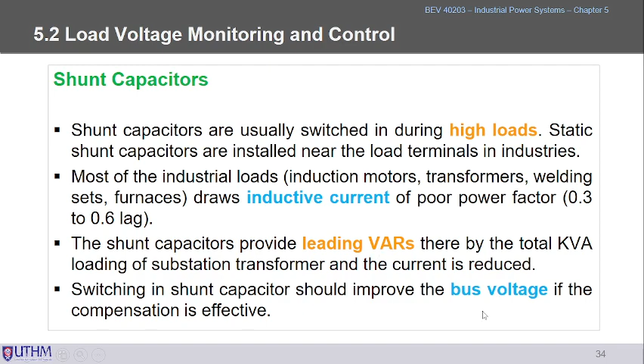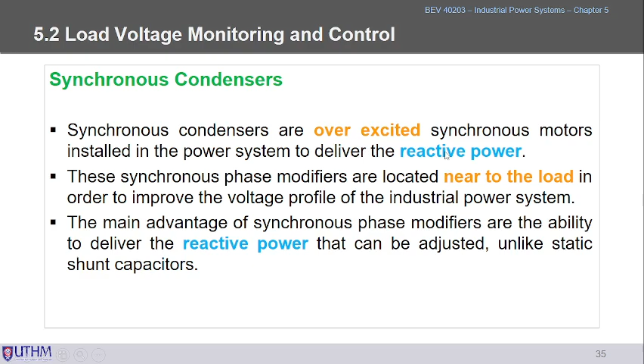Using the synchronous condenser, sometimes we call it an overexcited synchronous motor. An overexcited synchronous motor is the synchronous condenser. When the synchronous motor is overexcited, you can tune the power factor of the synchronous motor, and it will deliver reactive power. That means it will generate reactive power rather than consume it. Normally the synchronous motor or induction motor consumes reactive power, but for the synchronous motor we can adjust the exciter so that it becomes overexcited, then it will generate the Q.